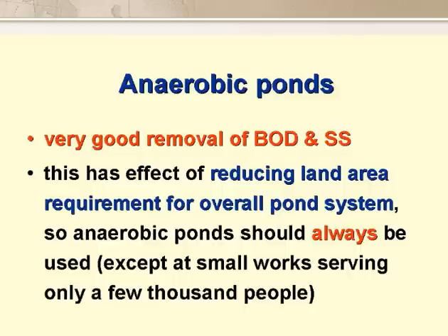Because anaerobic ponds have such good removals of BOD and suspended solids, incorporating them into a series of ponds has the effect of reducing the land area needed for the pond system. And so we should always use them, especially in warm climates. We would only not use them at small systems serving just a few thousand people.